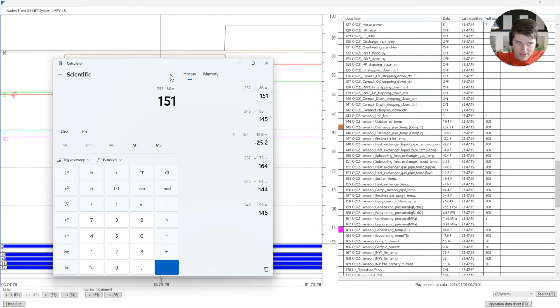Now for the guys, I'm going to break this down for you really quickly. Basic math skills, right? We learned that FOIL, first, inner, outer, last. Oh, almost forgot it there. Watch out. We look at math equations. We want to make sure that when we're doing these math equations it's different. Discharge superheat is your discharge temperature minus your saturation temperature. If you get those two mixed up, you're going to get a negative number. It's not going to make sense. However, in certain applications, it's important to know those differences because you can get negative numbers on certain stuff.